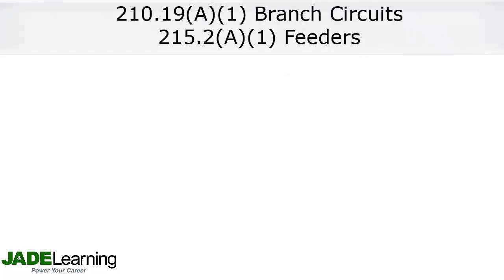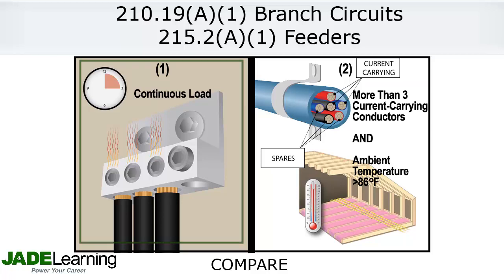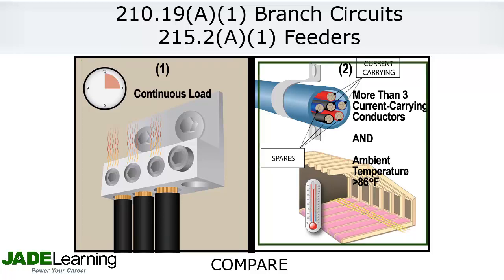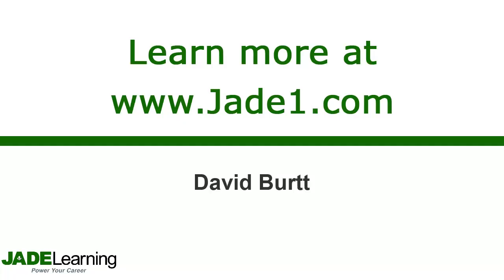The main point is that if a single circuit supplies a continuous load, has more than three current carrying conductors, and or is in an ambient temperature hotter than 86 degrees Fahrenheit, we should compare the size of the conductor needed to supply the continuous load with the size of the conductor needed because there are more than three current carrying conductors and or the ambient temperature is hotter than 86 degrees Fahrenheit. And we select the larger of the two conductors we get after making the comparison.